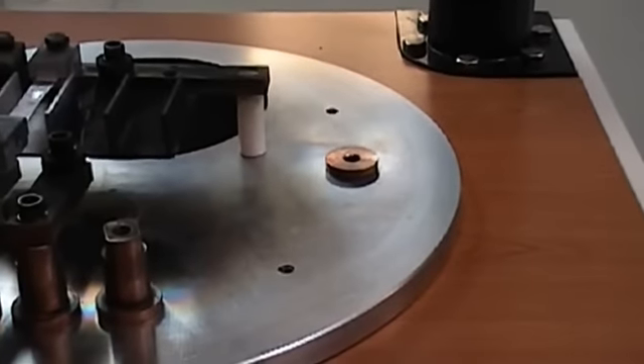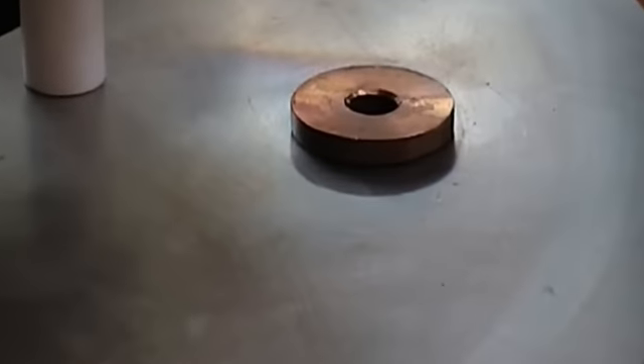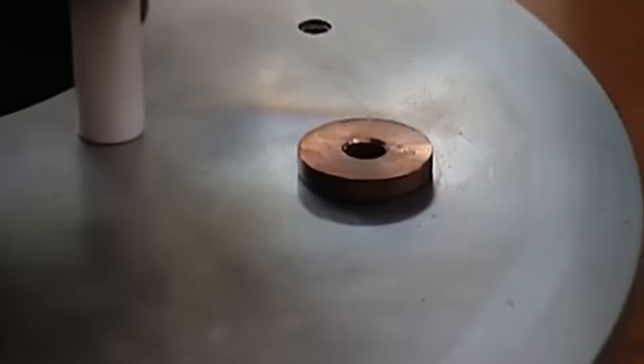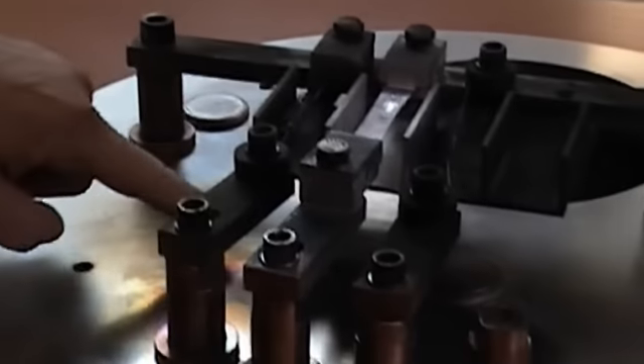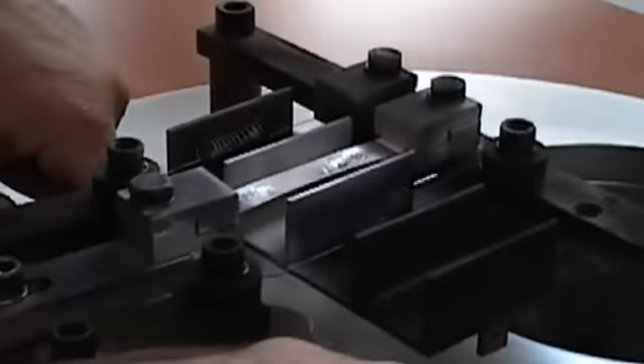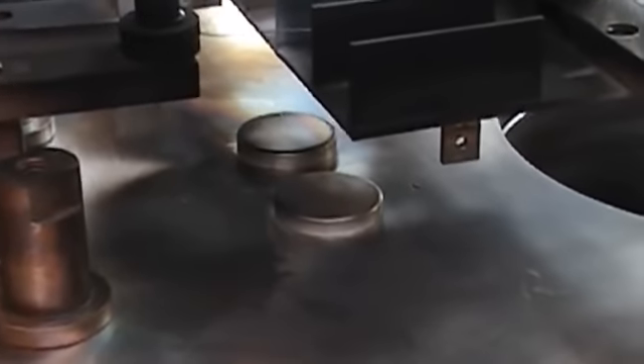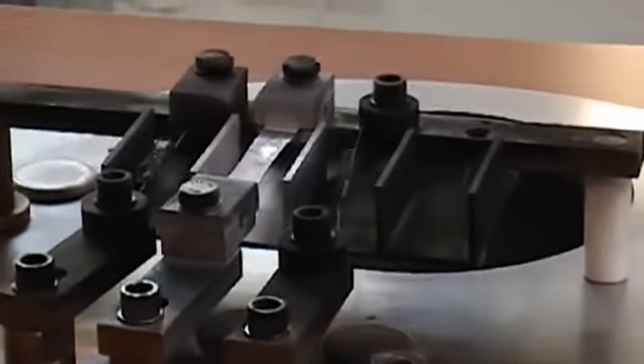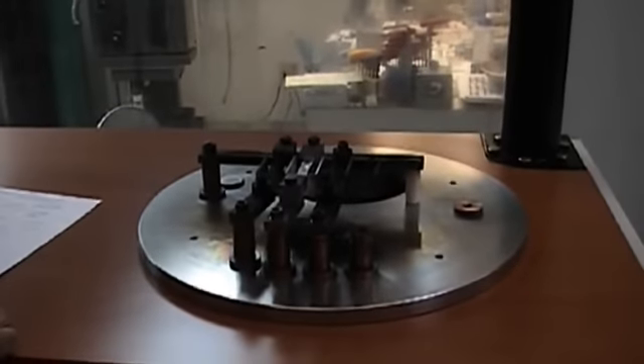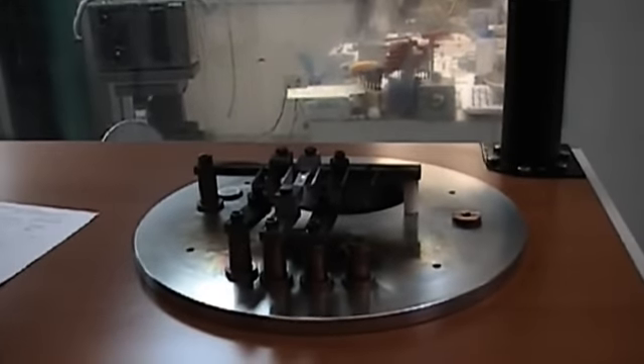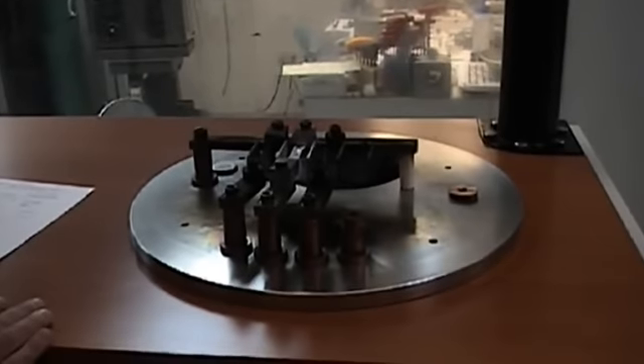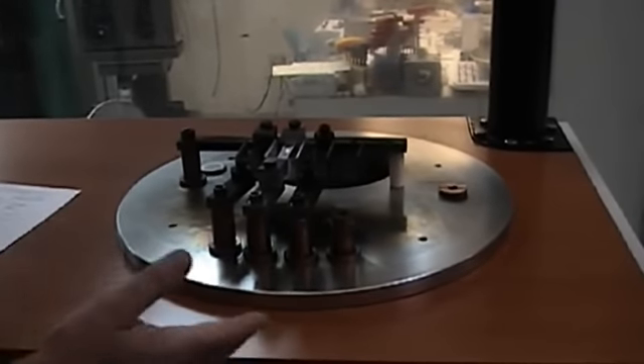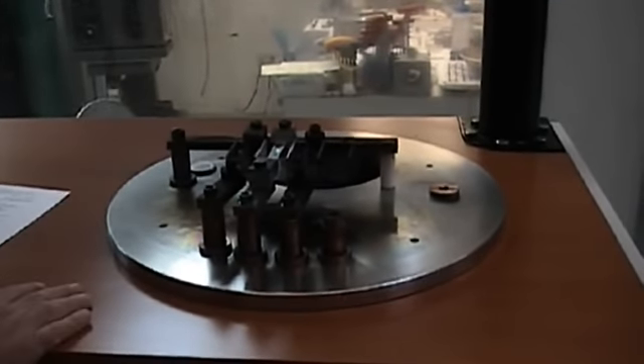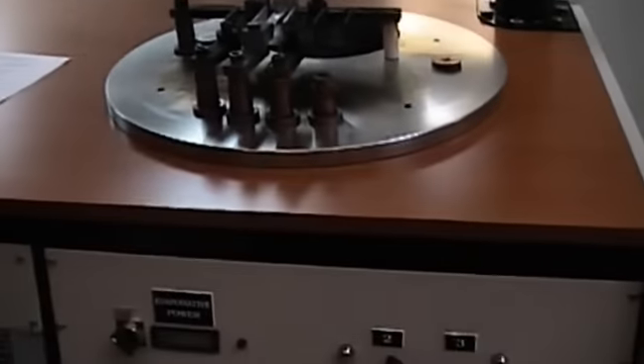What you see over here is our vacuum switch that's into the base plate. You still have one feed-through over here, one feed-through here, one feed-through here. Those are blanked. In addition, the top plate of the bell jar has a blank plate that could be modified to accept fixtures or tooling from up top, such as a film thickness controller, that type of stuff.